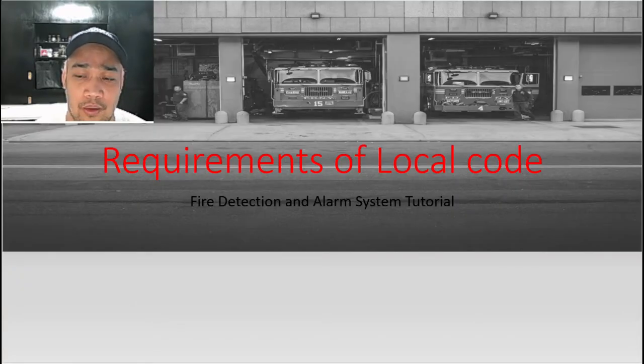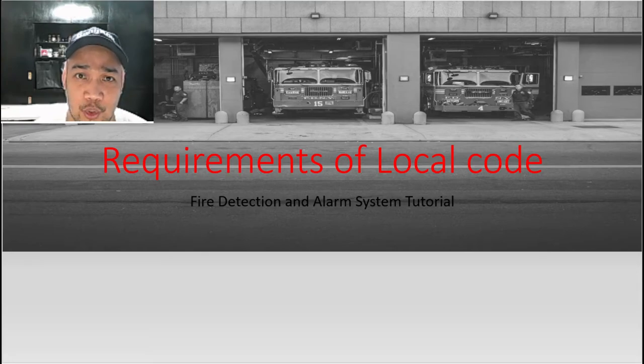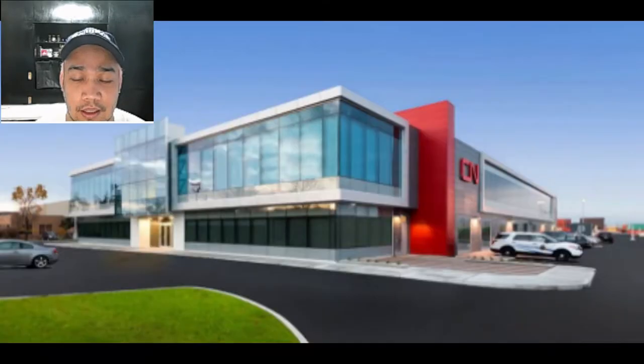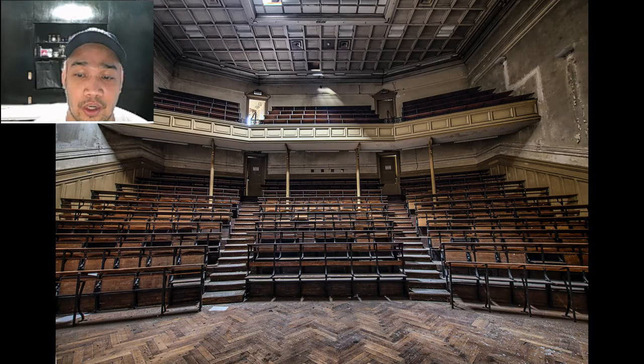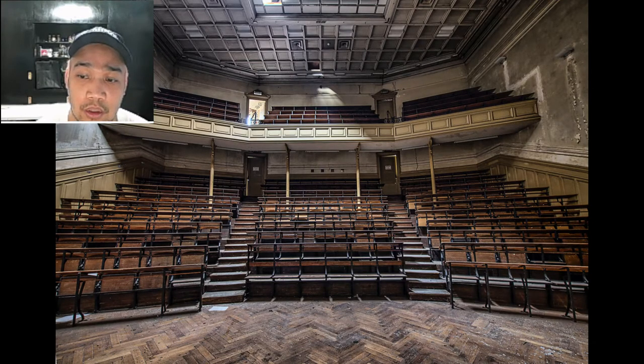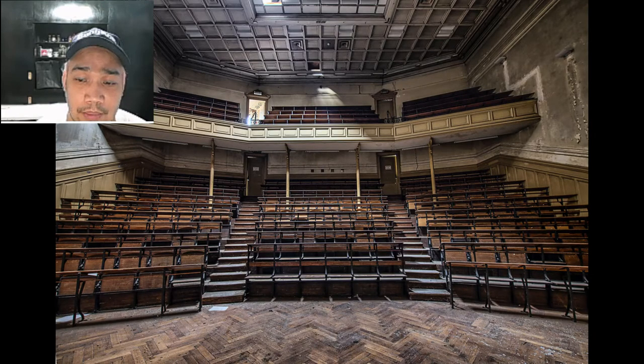Once the code is determined, you can now decide whether to include a fire detection and alarm system in the building. There are different requirements for every type of occupancy. For example, a fire alarm may not be required in a two-floor business occupancy but may be required in a two-floor assembly occupancy, depending on the applicable code.